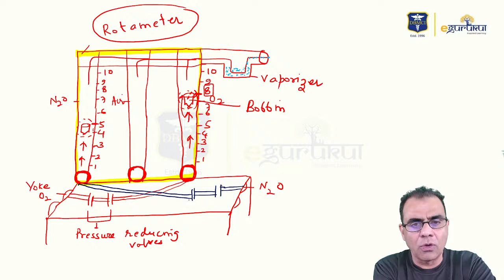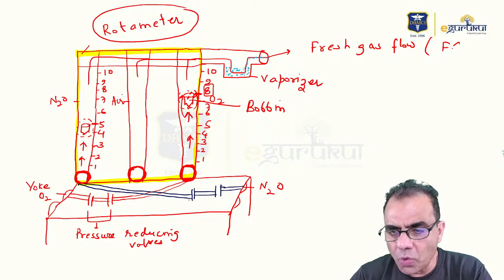And these evaporated particles will mix with this gas mixture. This volatile agent can be anything: halothane, isoflurane, sevoflurane, desflurane, whatever you want to use. So it will mix with these gases, and the final mixture which is delivered from the machine outlet is called fresh gas flow. Later we will be using the short form FGF, which is fresh gas flow. So this term we are going to use very, very commonly in future.